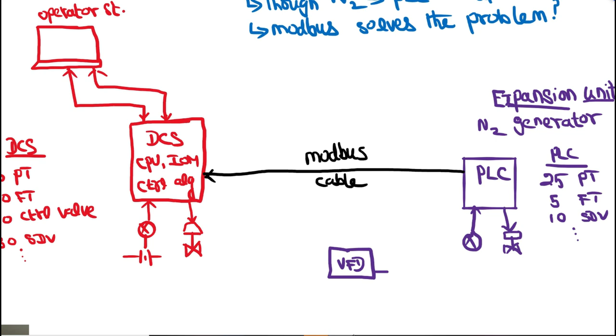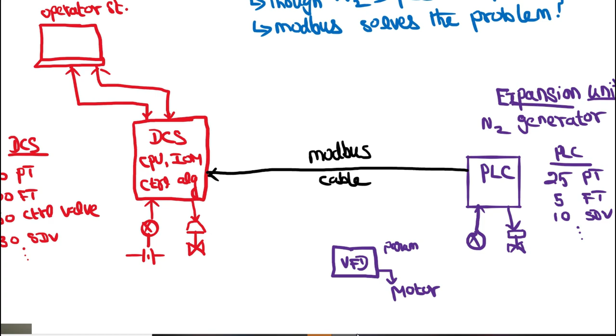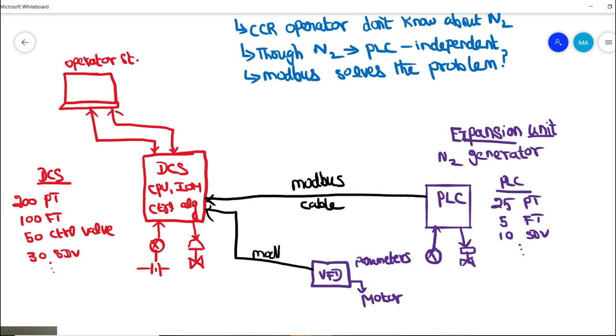And not only a single PLC control; if you have variable frequency drives in the process plant driving a particular motor, and you want to know the parameters of the motor like current, voltage, etc., these parameters can also be communicated to the DCS through the Modbus cable. So if you have different control systems, this Modbus communication protocol interconnects them. And these Modbus parameters are mandatory to be configured in the DCS and the control system as well.